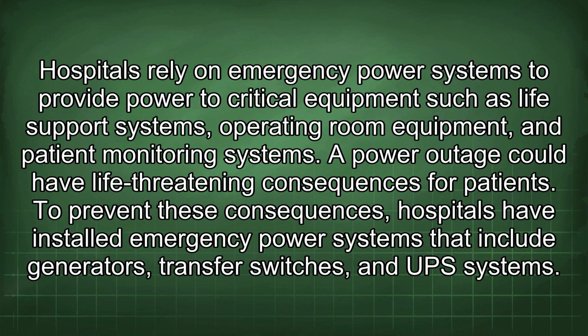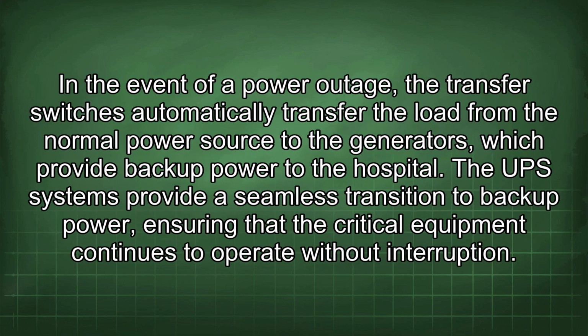Hospitals rely on emergency power systems to provide power to critical equipment such as life support systems, operating room equipment, and patient monitoring systems. A power outage could have life-threatening consequences for patients. To prevent these consequences, hospitals have installed emergency power systems that include generators, transfer switches, and UPS systems. In the event of a power outage, the transfer switches automatically transfer the load from the normal power source to the generators, which provide backup power to the hospital.